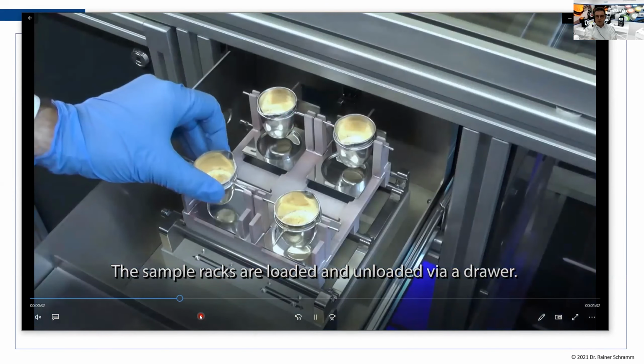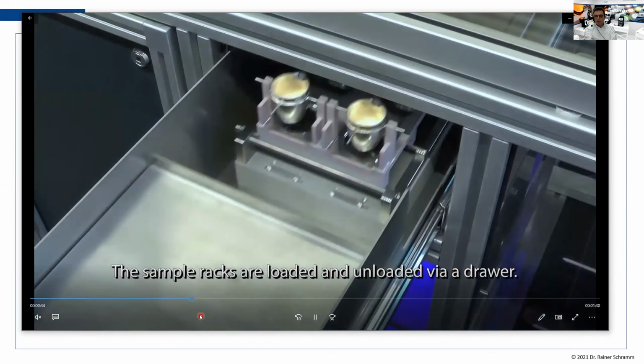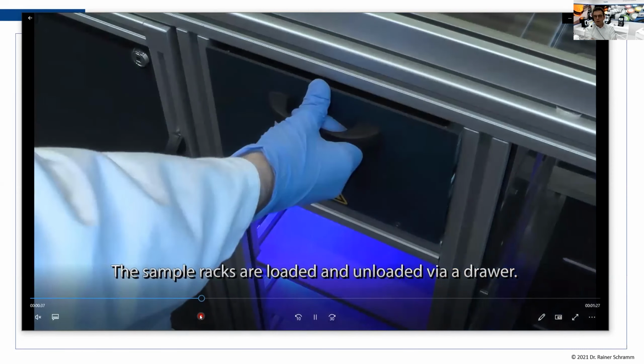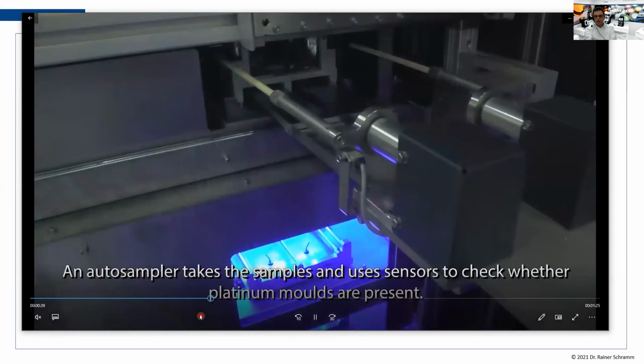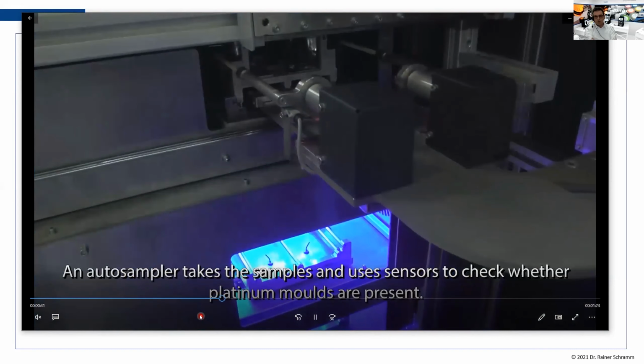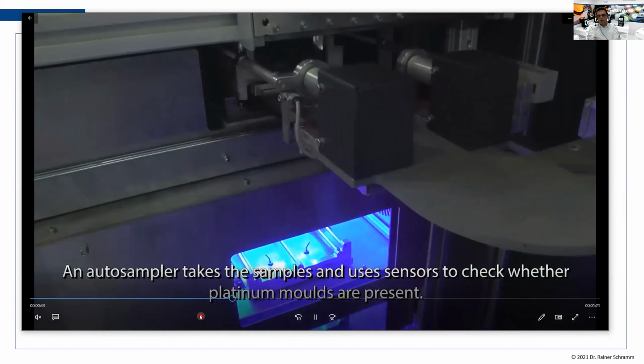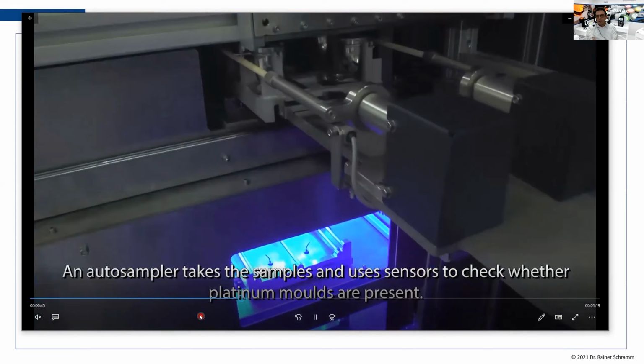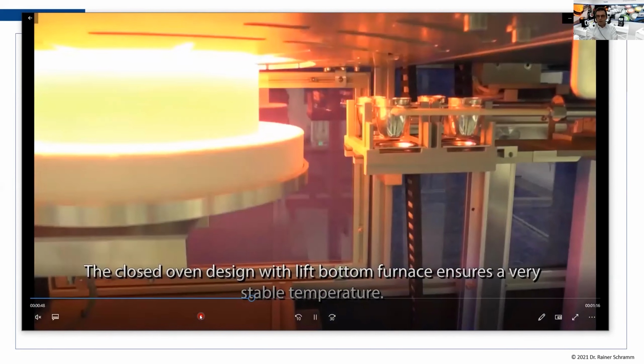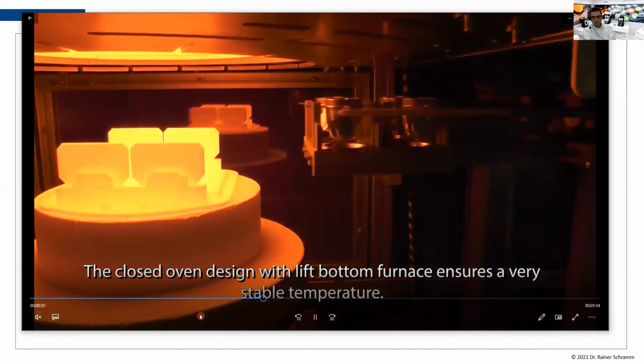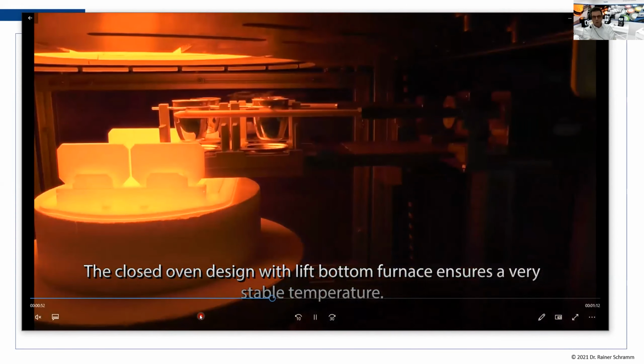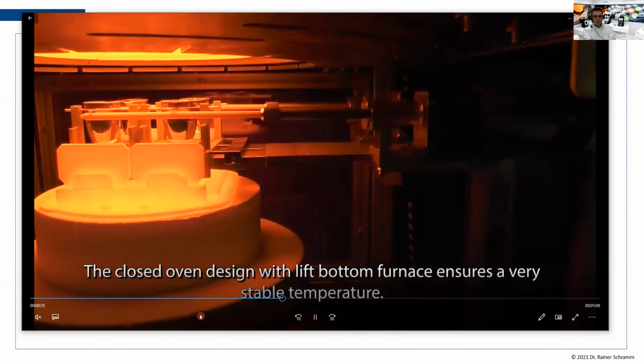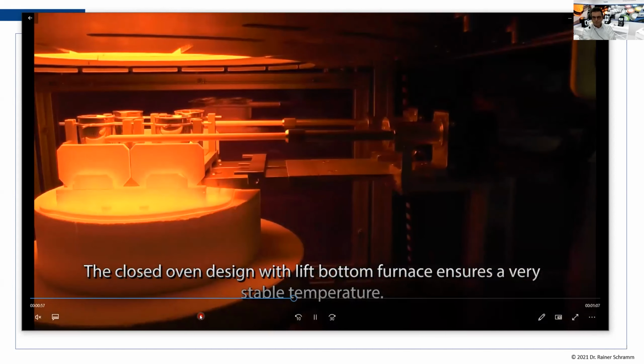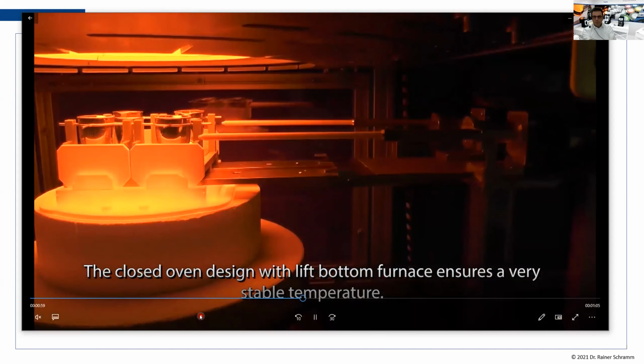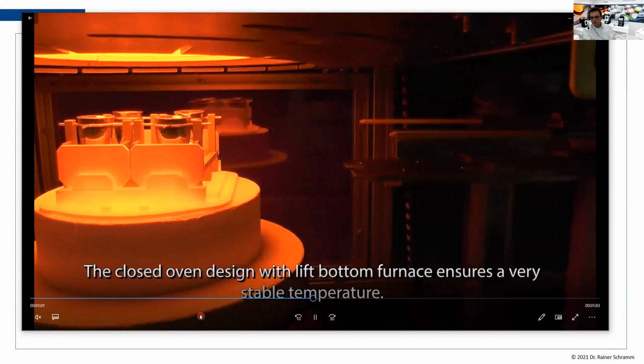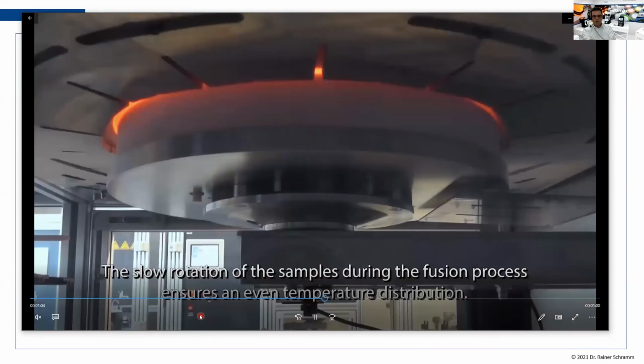Then here you have a drawer where you put the samples, and this is the user interface for putting the samples in and taking them back. Then the autosampler is doing the job. The only thing you do is introduce the samples, and that's it. The autosampler is also checking if the crucibles and the molds are there, so that no mold is missing. Then the autosampler places it into the furnace, and fully automatic, the furnace is closed and the temperature is heated up.